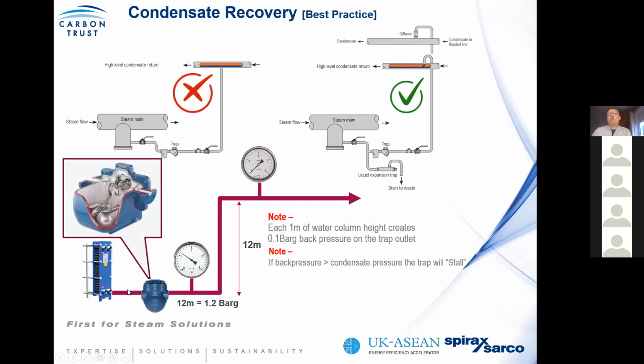In this scenario, we advocate you put in what's called a pump trap. The pump trap effectively uses steam: if the system is in stall mode, the pump trap goes into pumping mode and uses steam from an independent supply to pump the condensate back up to the user. So it's important to understand that steam traps only work under differential pressure. And if the pressure to the application is less than the back pressure being exerted on the trap, it won't work, and that's irrespective of manufacturer. So again, assess the application. And if you have scenarios where you have the problems we just mentioned, then you should be looking at the pump trap as a means of overcoming stall.